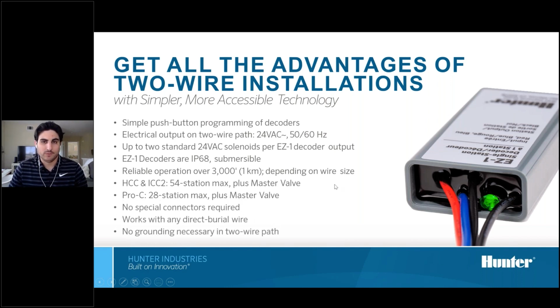And here are the last three most important features in my opinion: no special connectors required, though you obviously still want a professional grade connector. No special wire required, no twisted pair either. You could even use 18 gauge multi-strand wire for your 2-wire path. Obviously, as we talked about earlier, you won't be able to go as far as you would on a 14 or 12 gauge wire system, but it makes retrofits and existing systems a lot more flexible for installation. And then no grounding necessary within the 2-wire path, so there's lots of time and money back in your pocket, not having to get all these higher spec, high cost parts for your system.